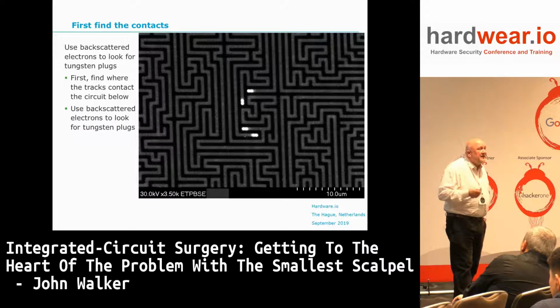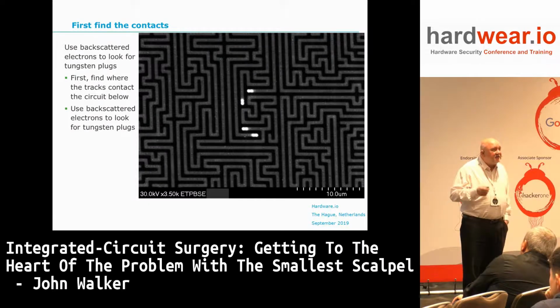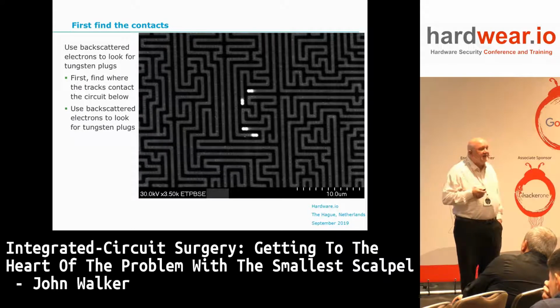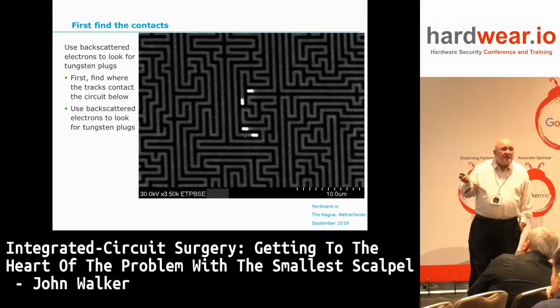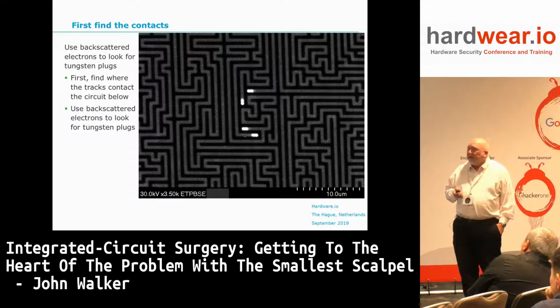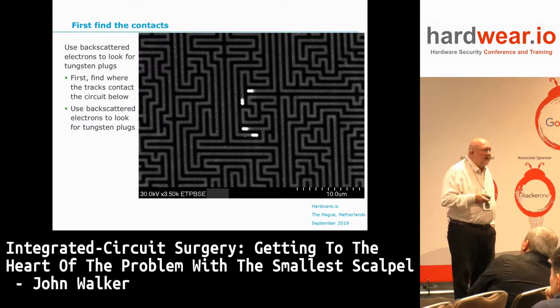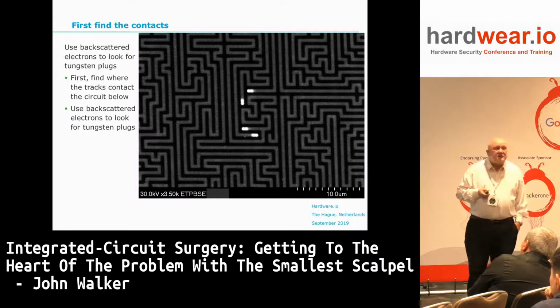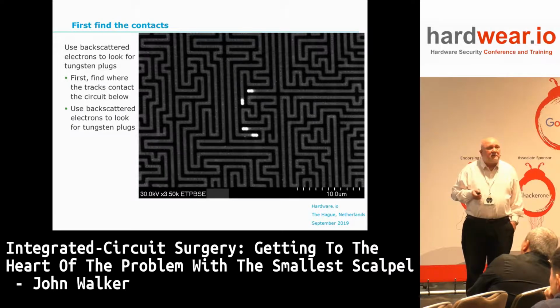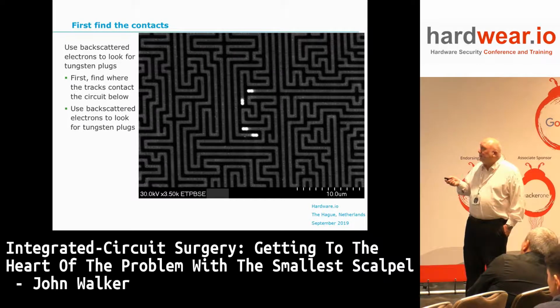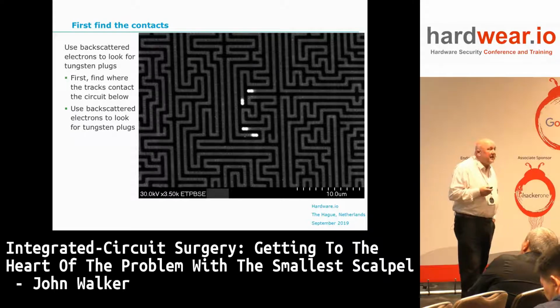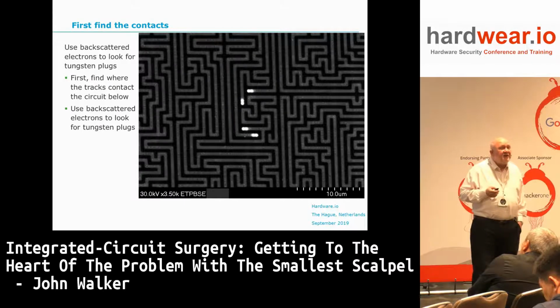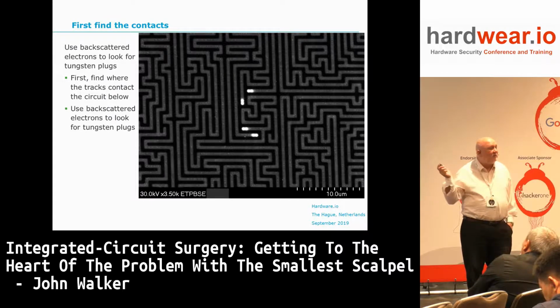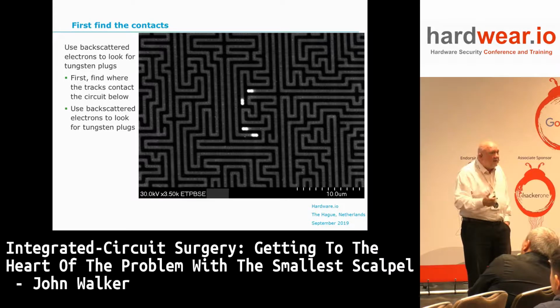The first thing is you would like to be able to recognize where the entire circuits of that shield are. And in this case, I've put the circuit not into the focused ion beam, or at least not using the focused ion beam, but in this case using the electron microscope. And if you use an electron microscope and you turn the voltage up to its maximum, 30 kilovolts normally, and you look at the circuit, then some things shine out at you. And these things which are shining out at you are the connections to the layer below. I'm sure that some of you know exactly what those things are. Any answers? Those are the tungsten plugs going down to the layers below.